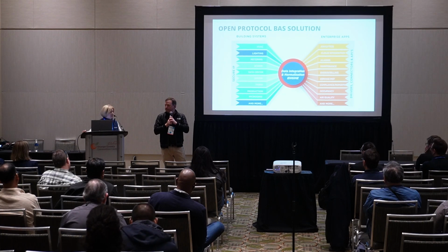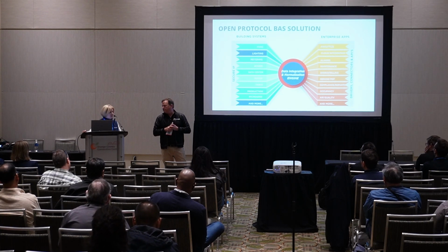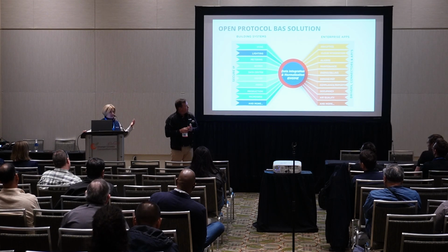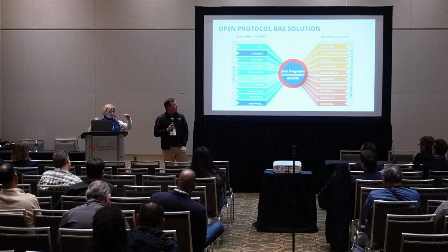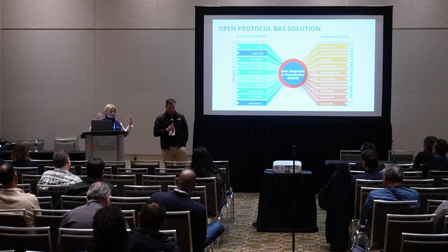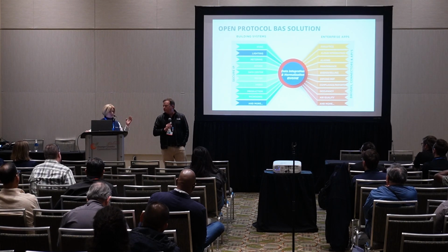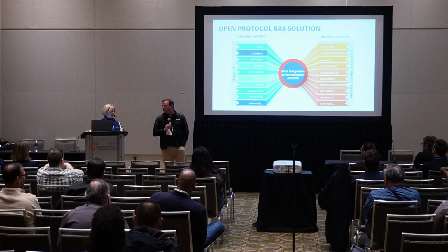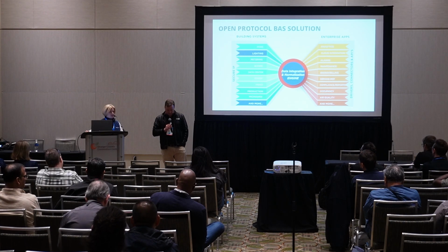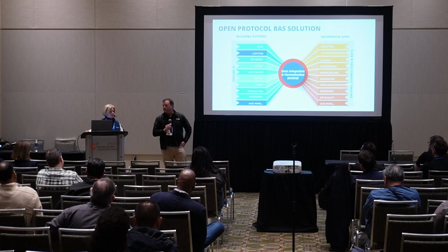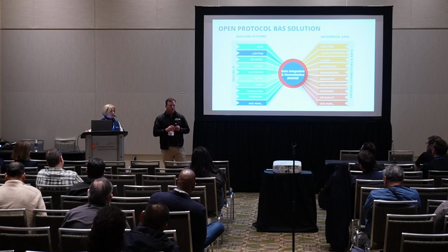The other classic one would be automated demand response, where you want to look at a whole zone, and you get the signal in from the utility and you want to pull back on the lights, dim the lights, and maybe move that air conditioning set point differently when your utility asks, hey, can you do that, so that we don't have to fire up the dirtiest plant. ADR is also something that big companies, big campuses, and the local utilities really appreciate if you've got that kind of control in your campus.